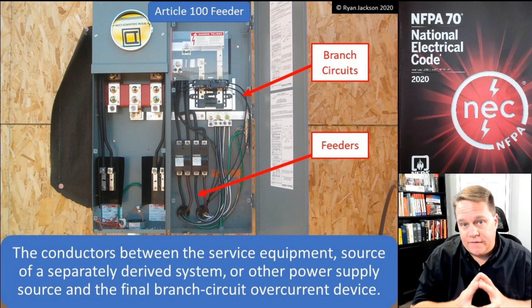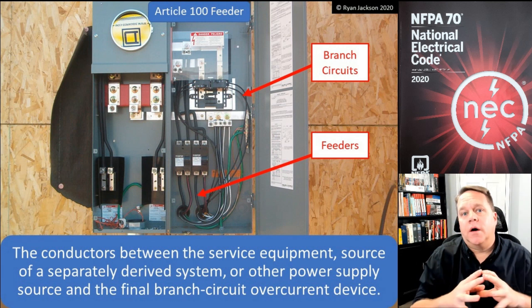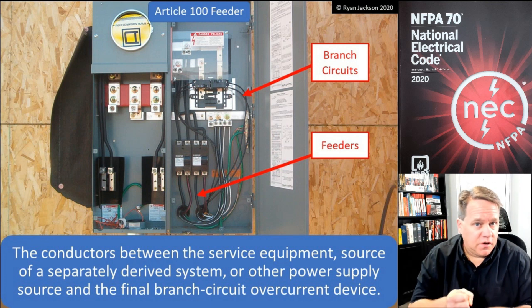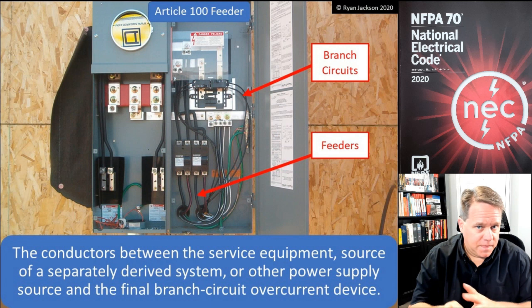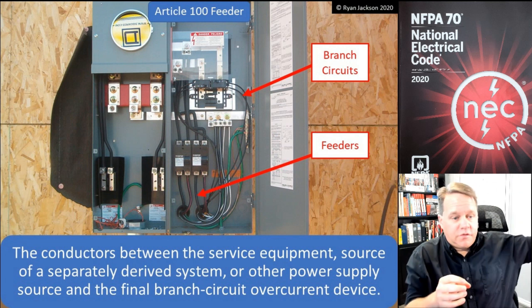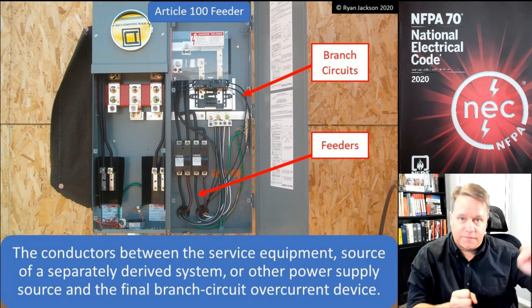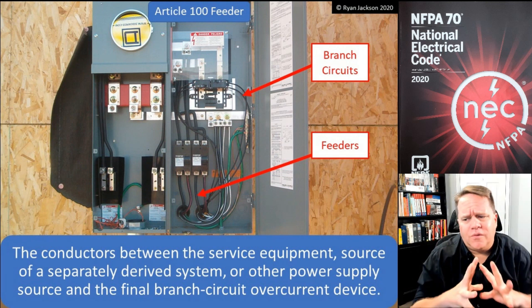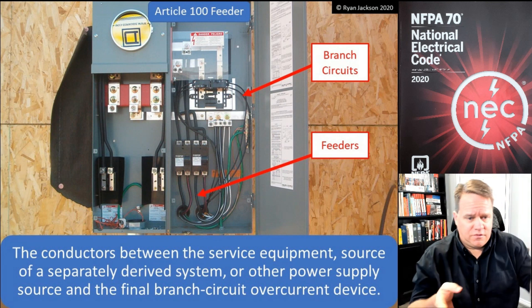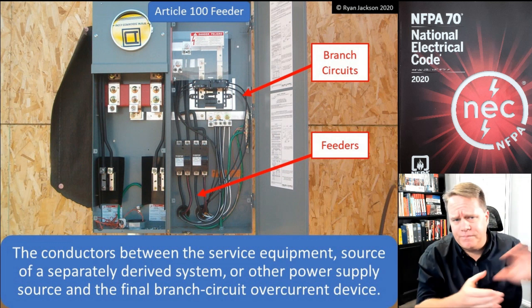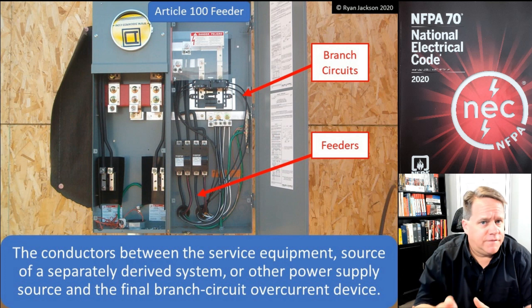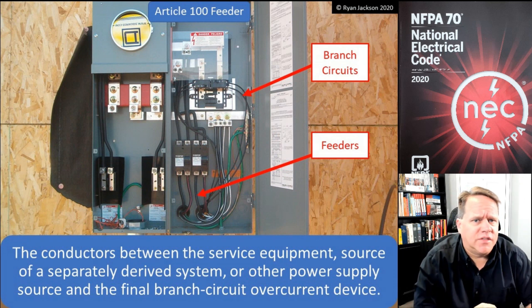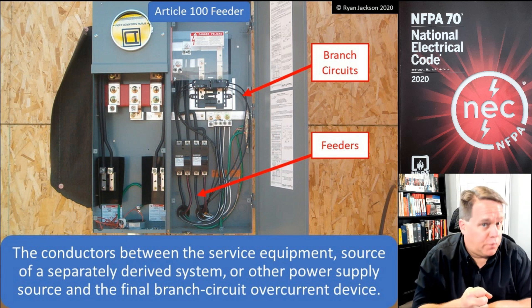It's really important that you understand this definition. When we talk about conductors for light and power, we break them up into three different types of circuits: branch circuits, feeder circuits, and service conductors. Service conductors come from the utility and end at the service disconnect — the first place where you can shut them off. Everything else (excluding control circuits and communications) is either a branch circuit or a feeder circuit.